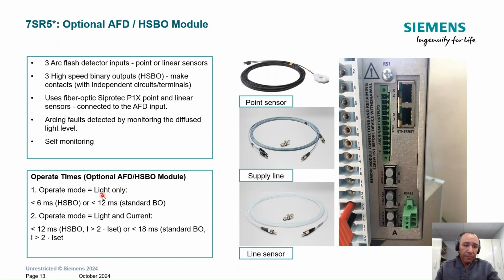Okay, you have 2 options. You can have the light alone as a trigger for the protection, and the device, using the high-speed binary outputs, can trip in less than 6 milliseconds. When you combine light and current, the device can trip in less than 12 milliseconds.